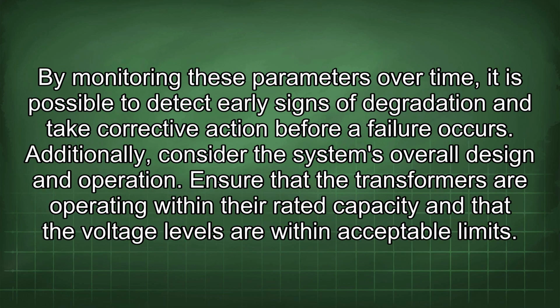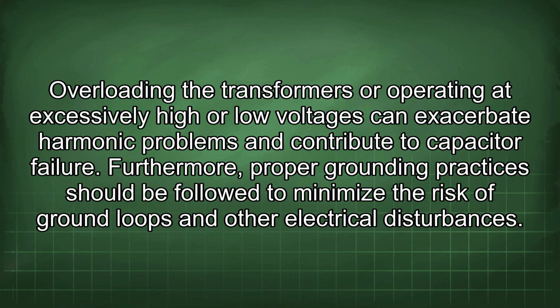By monitoring these parameters over time, it is possible to detect early signs of degradation and take corrective action before failure occurs. Additionally, consider the system's overall design and operation. Ensure that the transformers are operating within their rated capacity and that the voltage levels are within acceptable limits. Overloading the transformers or operating at excessively high or low voltages can exacerbate harmonic problems and contribute to capacitor failure.